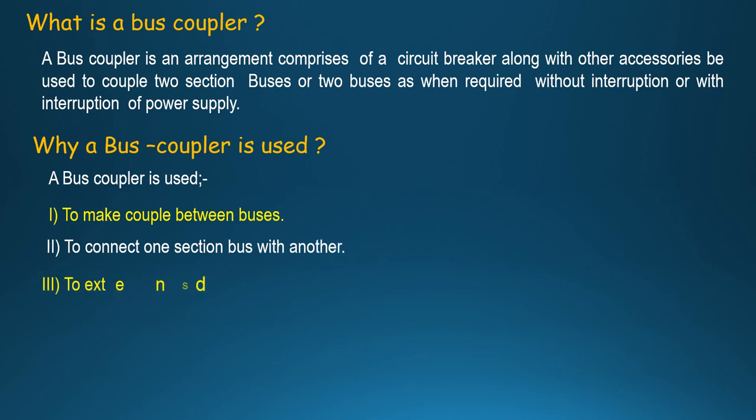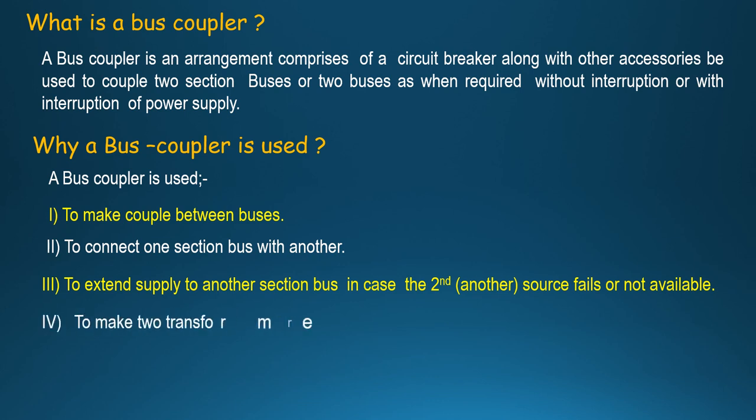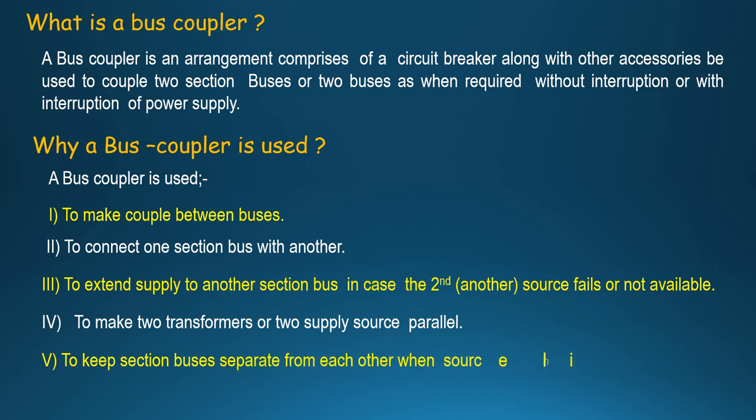to extend supply to another bus in case the second source fails or is not available, to make two transformers or two supply sources parallel, to keep section buses separate from each other when source lines or transformers will not run parallel.